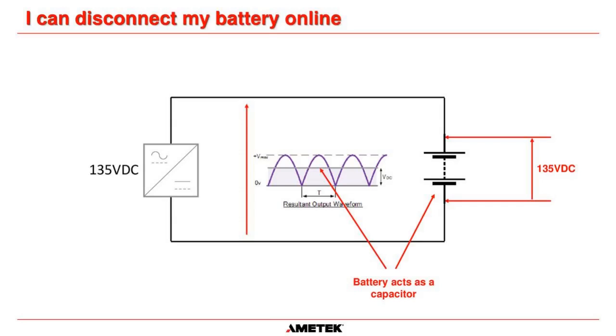Now, many charger manufacturers, especially older chargers, didn't have the DC filtering that modern day capacitors have. In fact, some chargers didn't have any capacitors inside them for filtering purposes. Okay? So if you look at this picture here, if you have an unfiltered charger, you have AC coming in on this side here, 135 volts, and that is a sinusoidal waveform. And the way that the charger creates DC is it takes this portion of the AC and flips it up above the 0 volt line, which is basically DC. And you can see that in this example here.